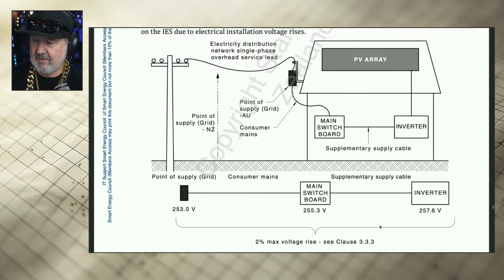It's also recommended, depending on what lines companies or DNSPs require, to have maybe 1% per segment — 1% from inverter to main switchboard, then 1% from main switchboard to point of common coupling. In some jurisdictions, I know Essential Energy actually have 3 segments: main switchboard, subboard, submain — basically 3 segments. Anyone in Essential Energy will know those requirements. Often these are part of your online application — you need to put in these values. I believe some have calculators, so you can enter the cable size and length, and it will give you a traffic light solution, go or no go, on whether your application will be approved. So there you go.